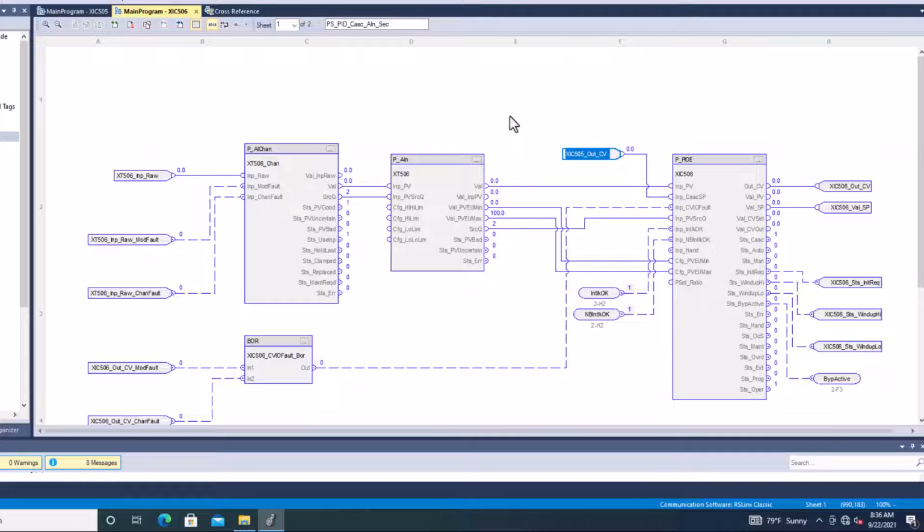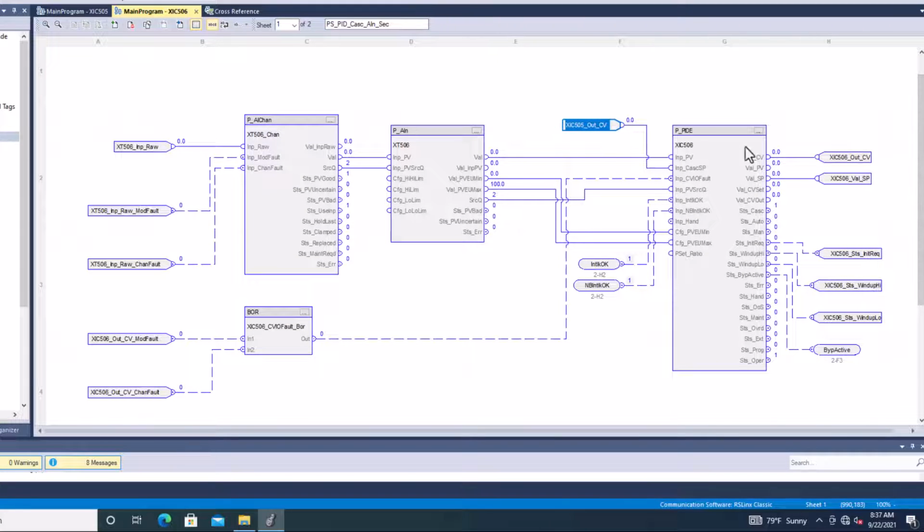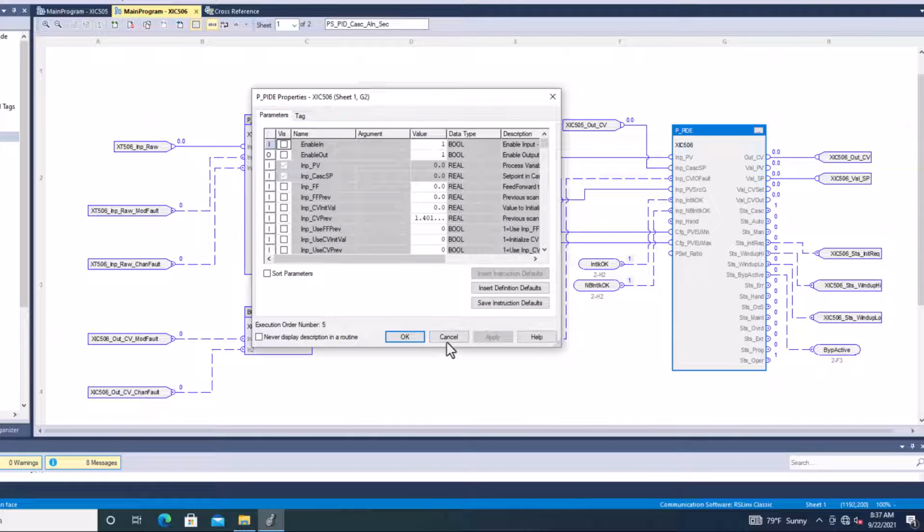You start the PID loops in auto, and then you transition them into the cascade loop. Okay, and that's basically because you want to have independent control, have everything working, and then you can fall into cascade. And then cascade will obviously be a more defined control. Think about it as the tuning behind this should be really, really specific, right?